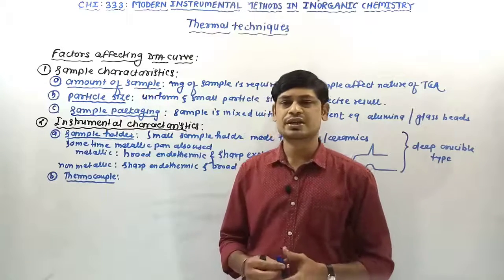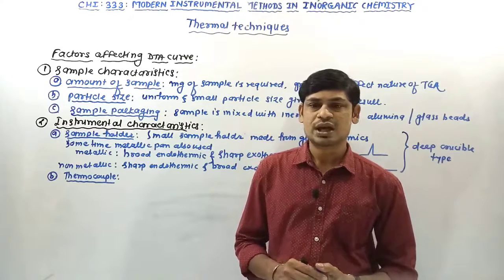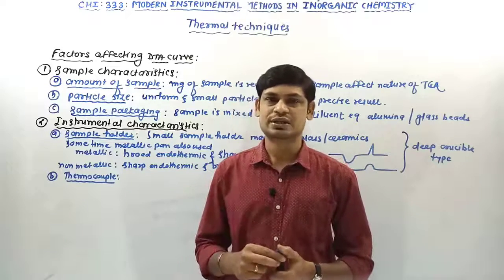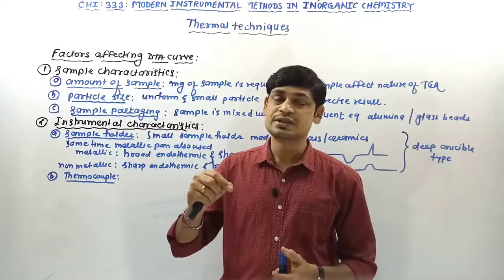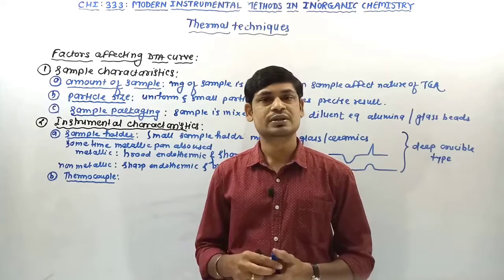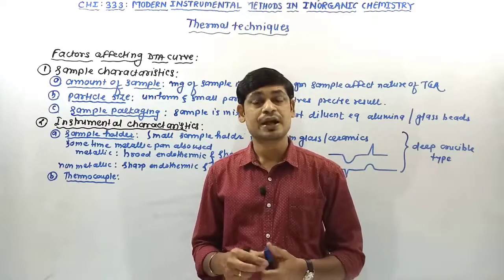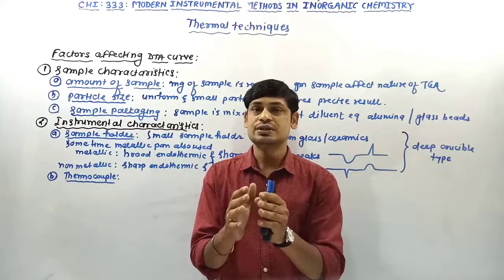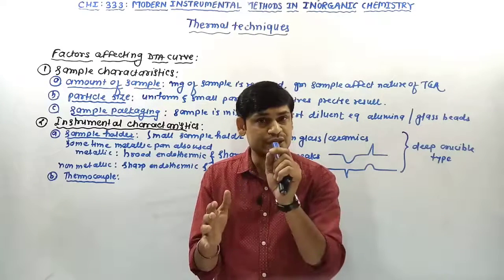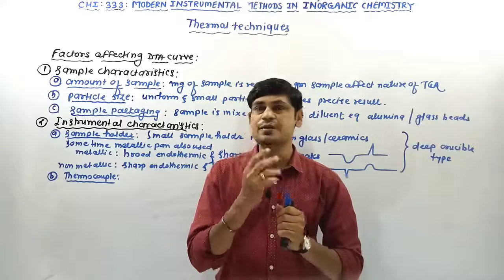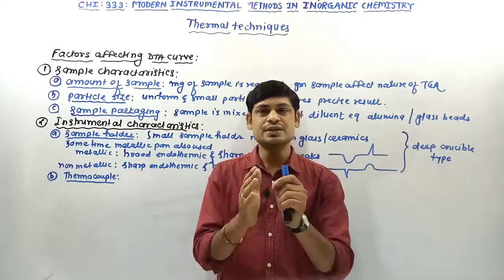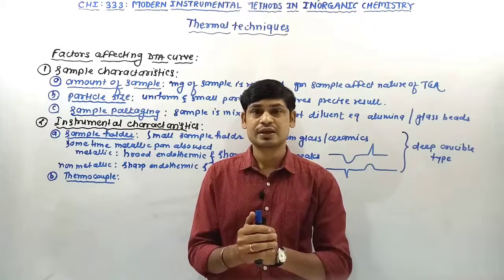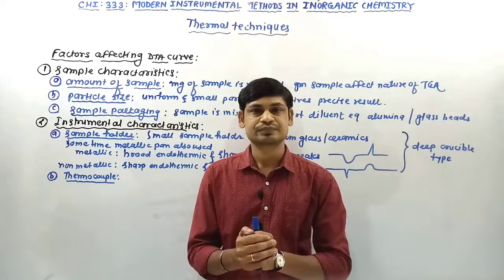In most of the DTA, the thermocouple is directly in contact with the sample material. It means it is present inside the sample holder. According to our previous discussion, depending upon the location, or you can say the position, of the thermocouple, two types of DTAs are there. One is the heat flux DTA, and the second is the classical DTA.